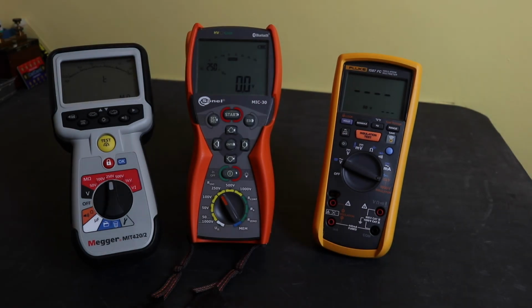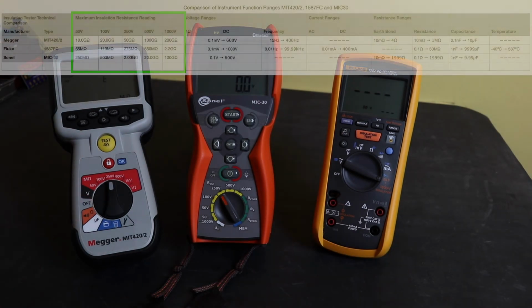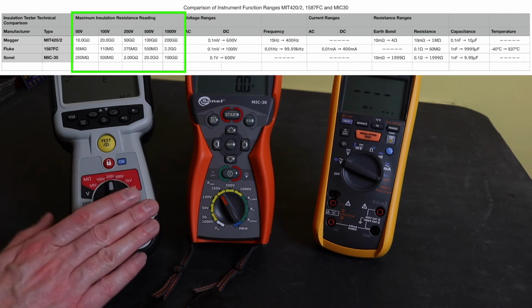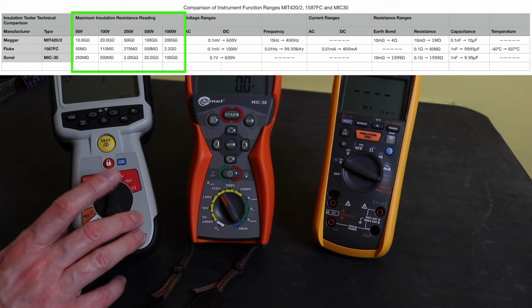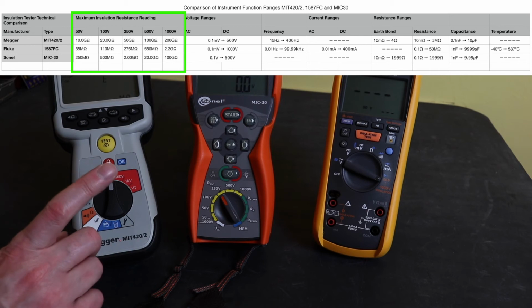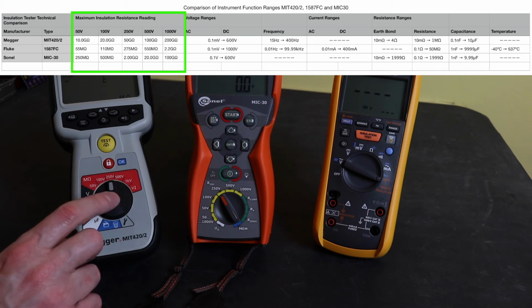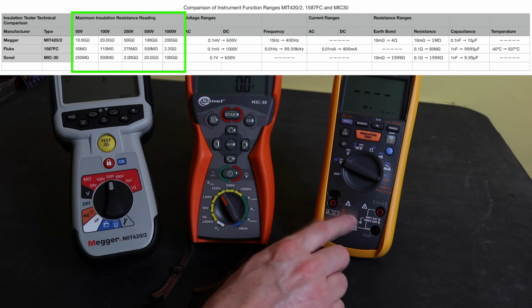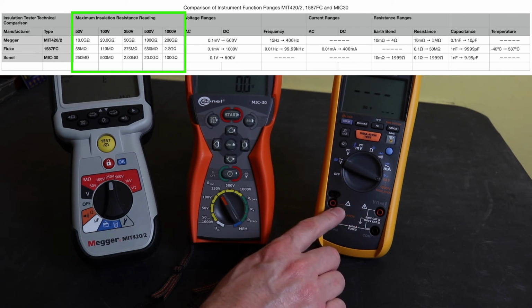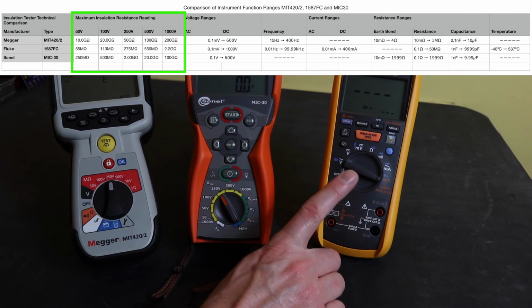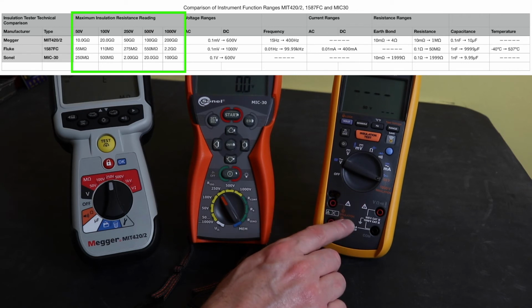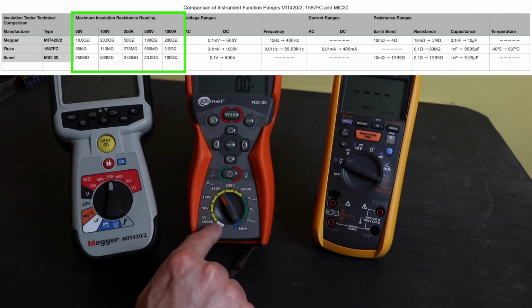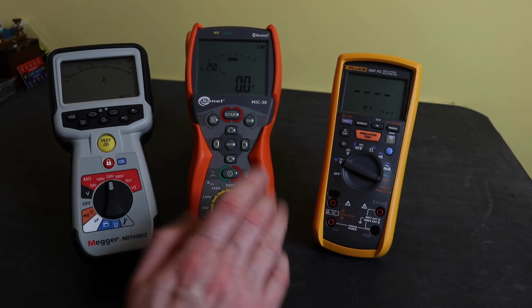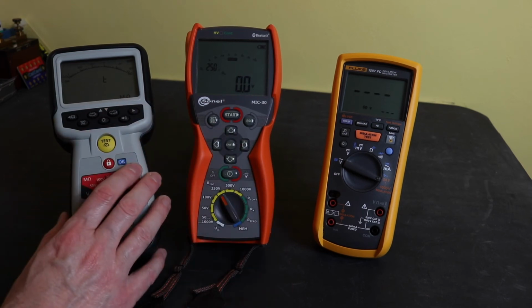In terms of test range capability of these instruments for insulation testing, 100 gigaohms at 500 volt test voltage. For the Megger, goes up to 200 gigaohms at 1000 volts. For Fluke over here, it's 550 megaohms at 500 volts, going up to 2.2 gigaohms at 1000 volts. And for the MIC-30, it's 20 gigaohms at 500 volts, going up to 100 gigaohms at 1000 volts. So the Megger wins out, hands down on that.